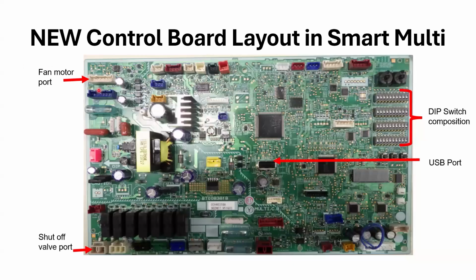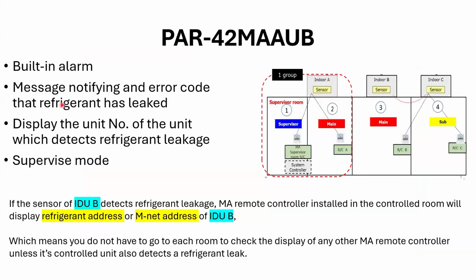So fan motor port connections over here, which is pretty much where they were before. I don't see any difference there. Shut off valve. Here are the liquid and vapor valves in the outdoor unit to do the pump down, recovery, right? And the alarm. So that's where they're powered at, the connections on that board. The lower port for the fan motor changed from, oh okay, wow. We changed colors on the fan motor connectors from white to blue. There you go. Built-in alarm.